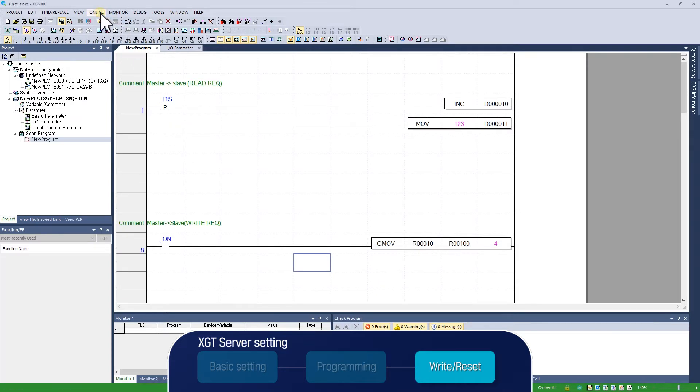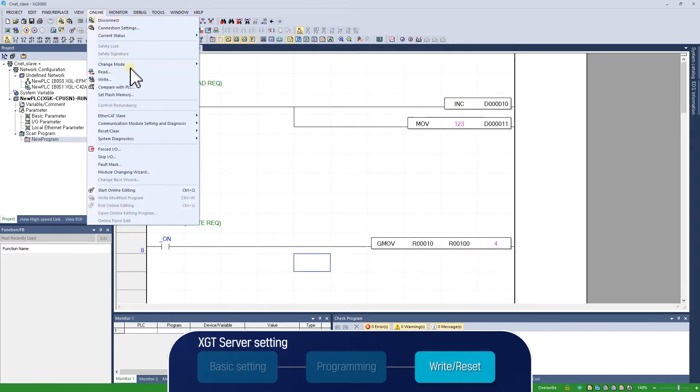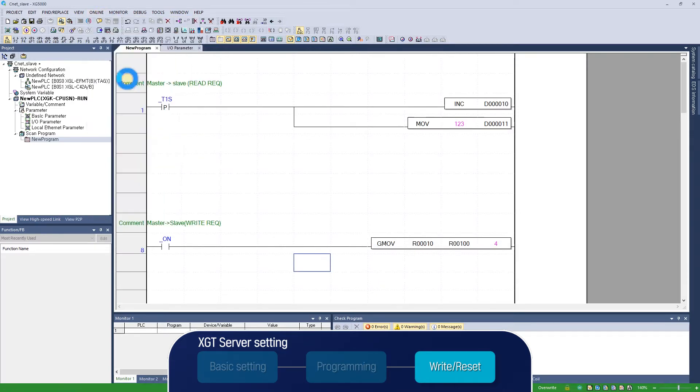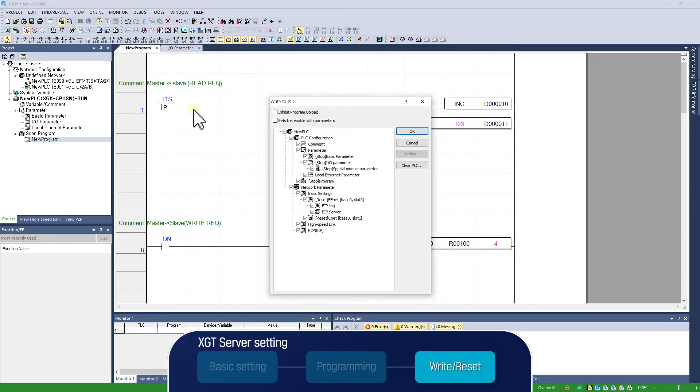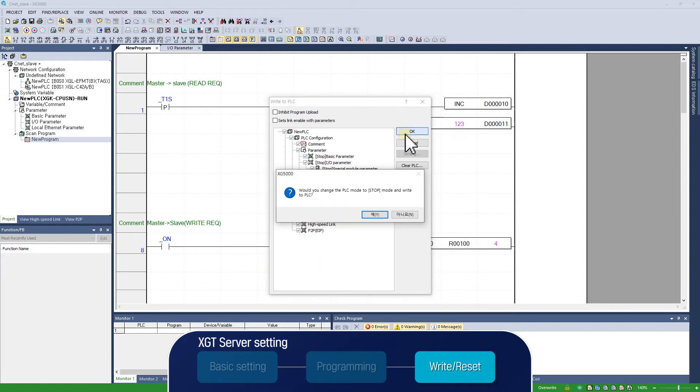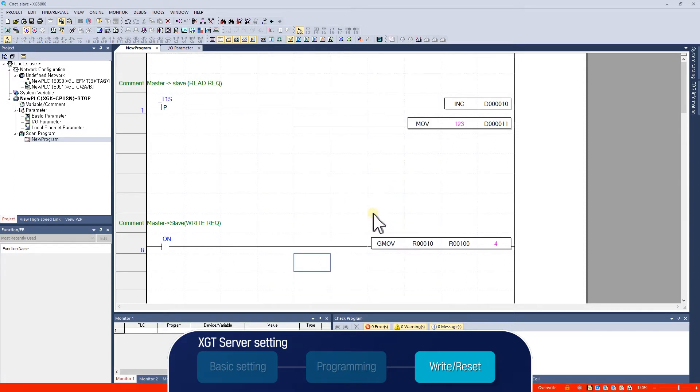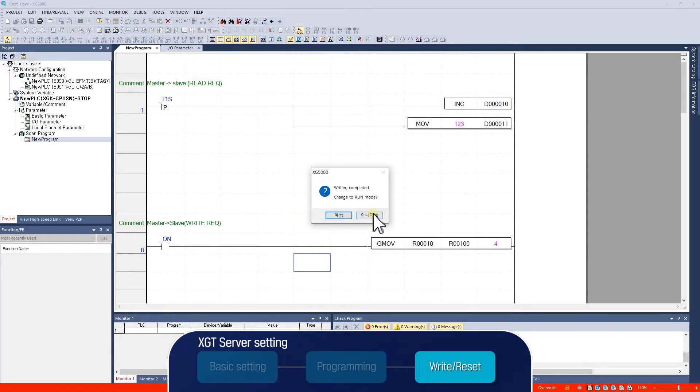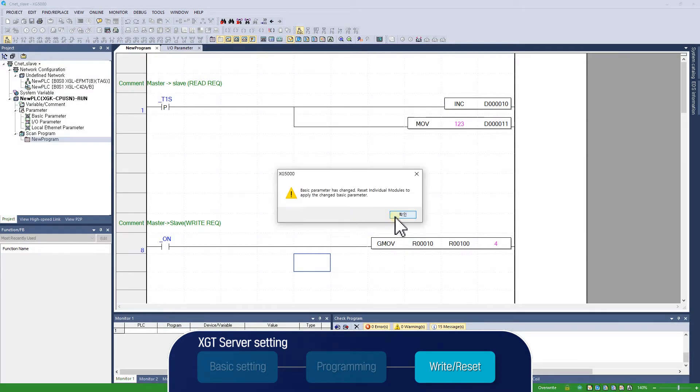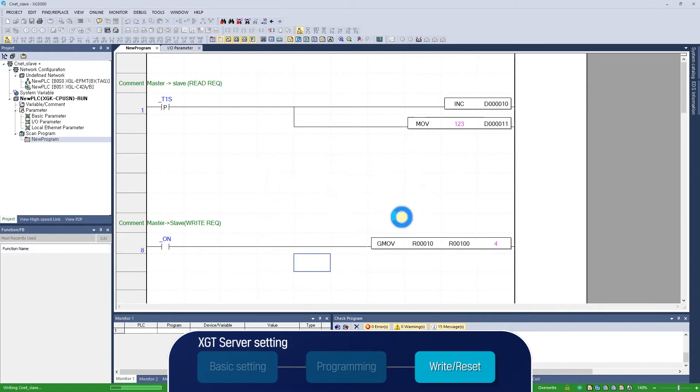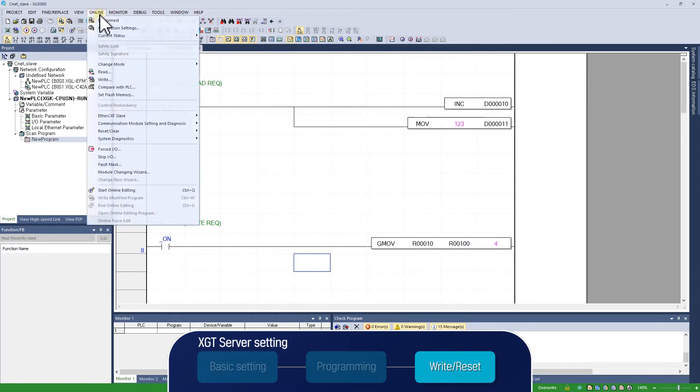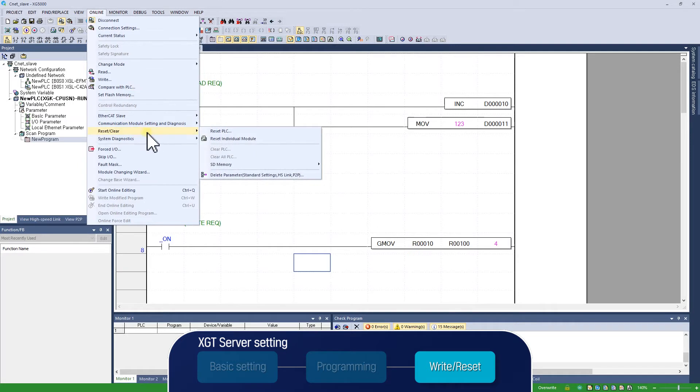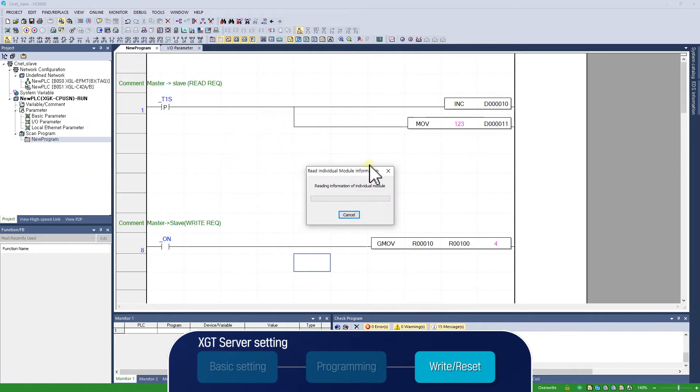Click online write button in XG5000 to download the basic parameter and program to the PLC. At this time, if program is checked in Download tab, please download the program, paying attention to stopping of PLC operation. To apply the changed basic setting parameters, click online, reset clear, individual communication module reset to reset module.